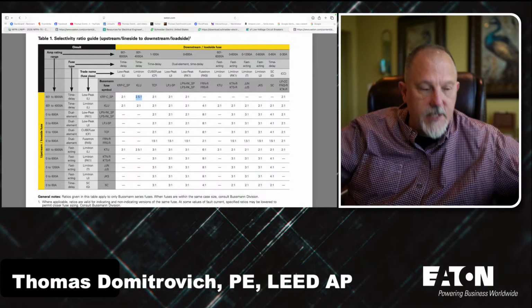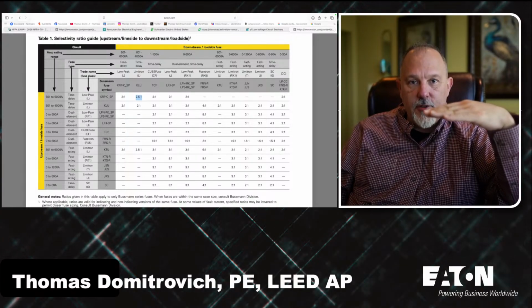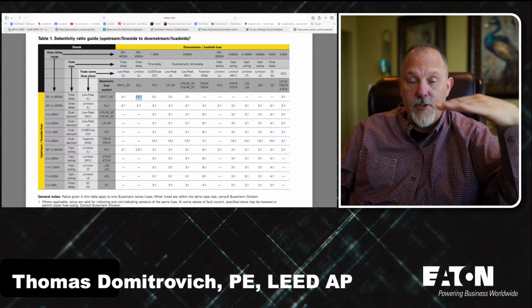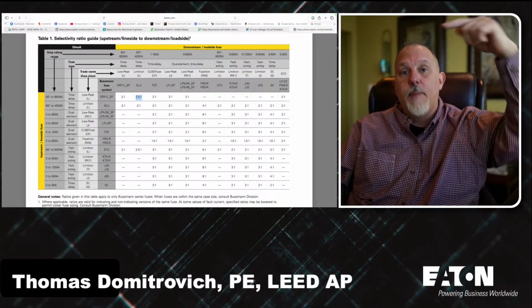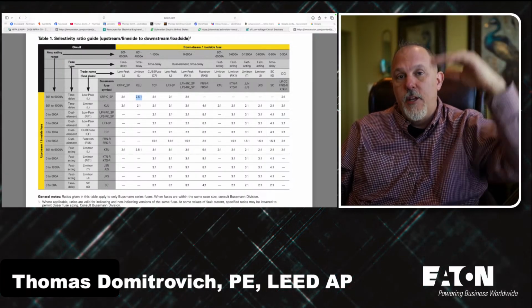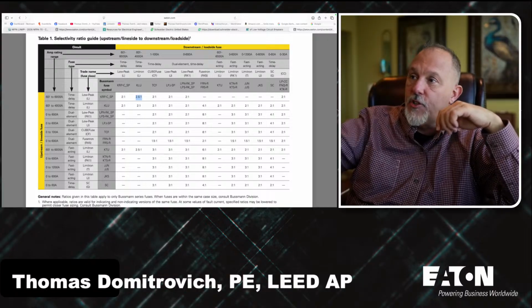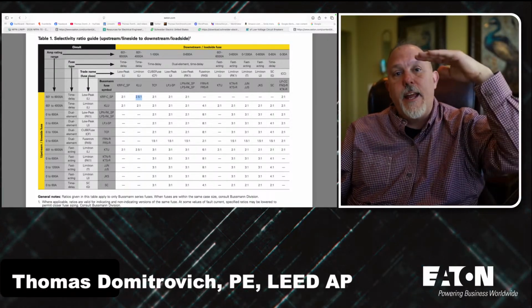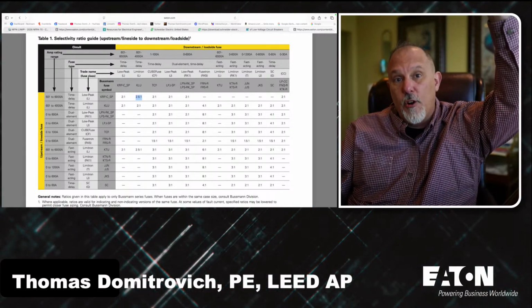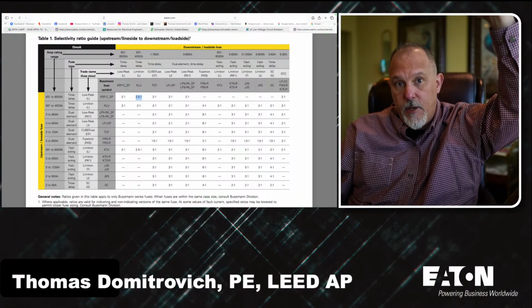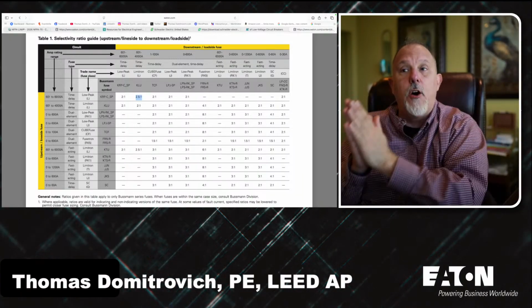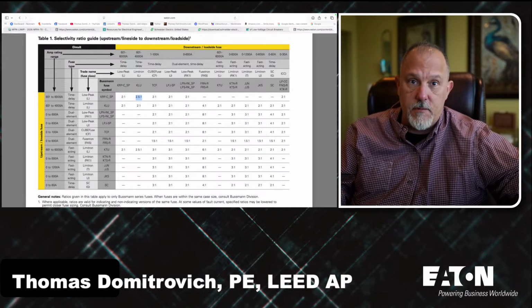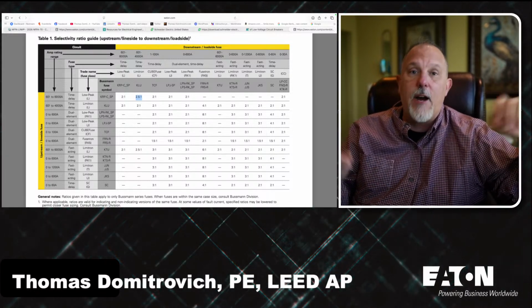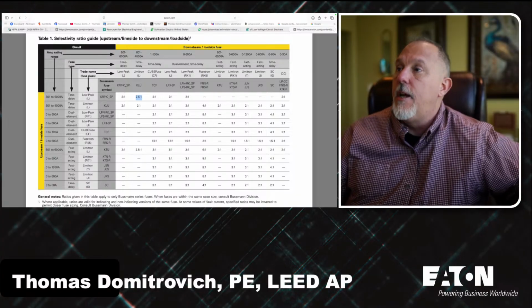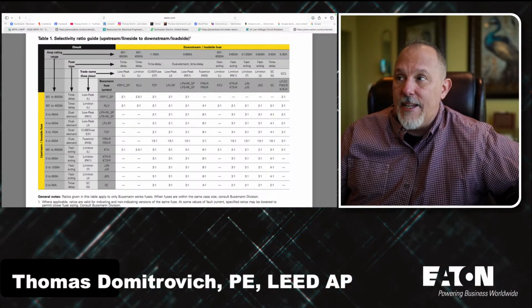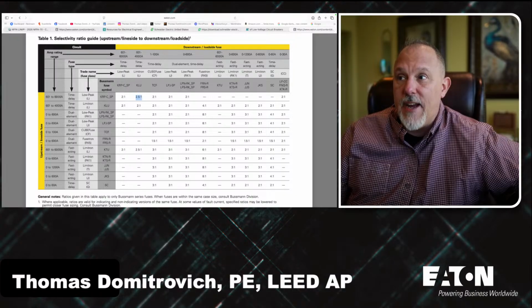Here's what a 2-to-1 ratio means. If I have a 100 amp breaker downstream or a 100 amp fuse downstream, I need a 200 amp or larger upstream. So if I had a 100 amp downstream and it was a 2.5, I'd need a 250 amp or larger fuse upstream to get selective coordination all the way up to 200,000 amps. So it doesn't matter how much current you pump through these fuses, as long as you maintain, in this case, 2 to 1, but also 2.5 to 1.